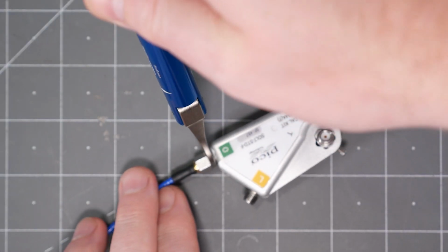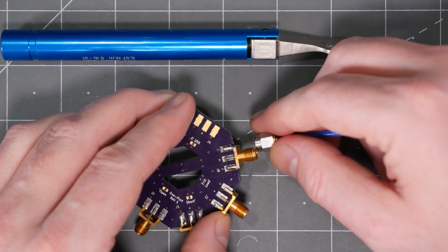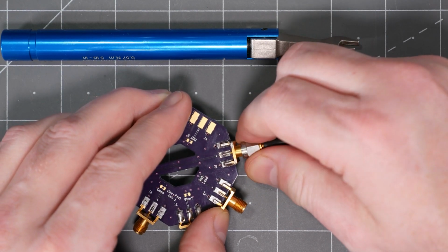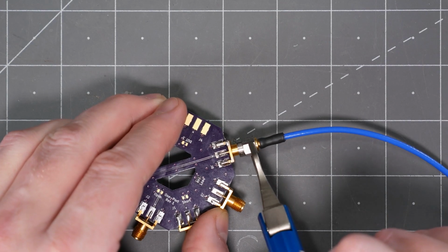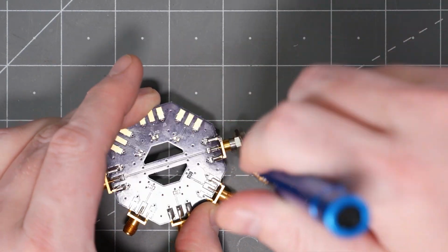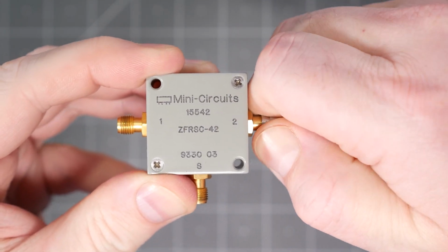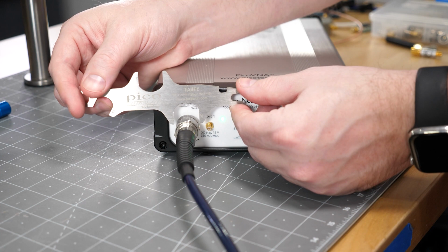Also notice that I'm using this fancy torque wrench. These are very important for two reasons. First, it prevents damaging the connectors, and second, it provides repeatability in your measurements. Brass and stainless steel fittings have different maximum torques. If mixing types, then go with the max torque for brass. If you do not have a torque wrench, then go barely past finger tight. Pico Technology includes this tool in their kit, but I still recommend a torque wrench.